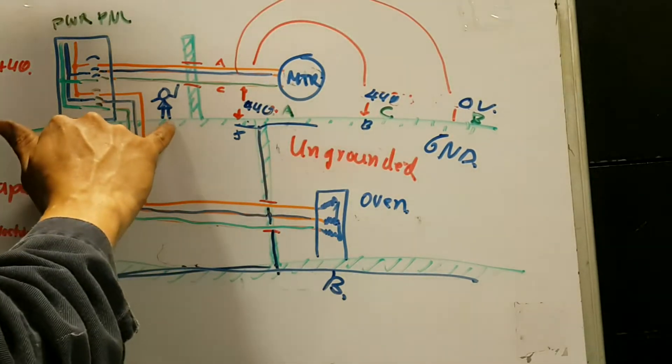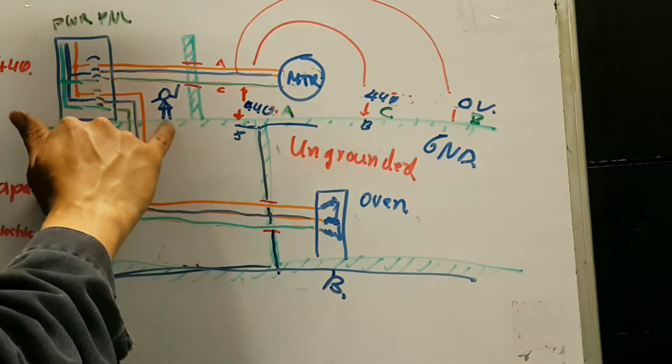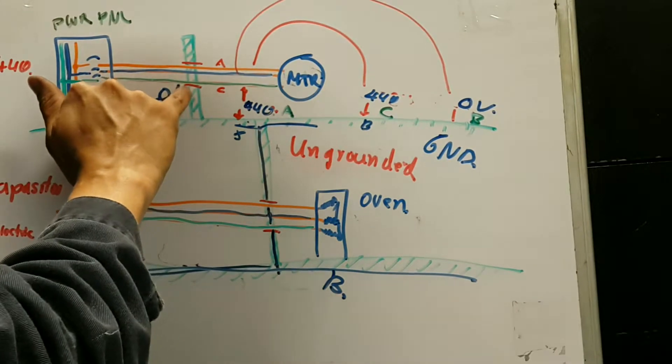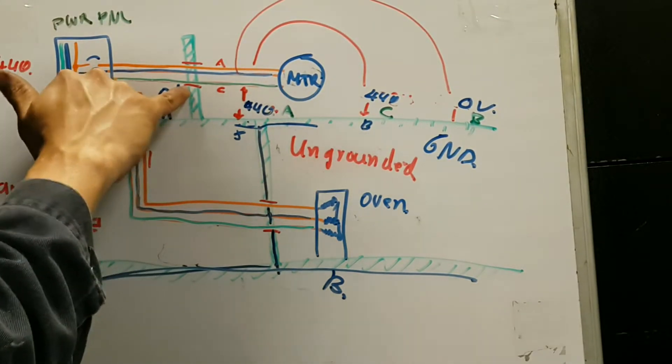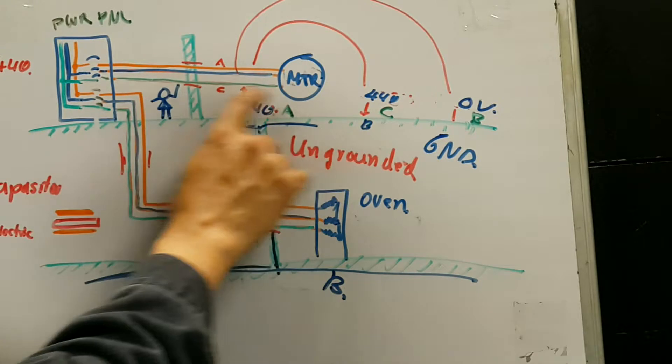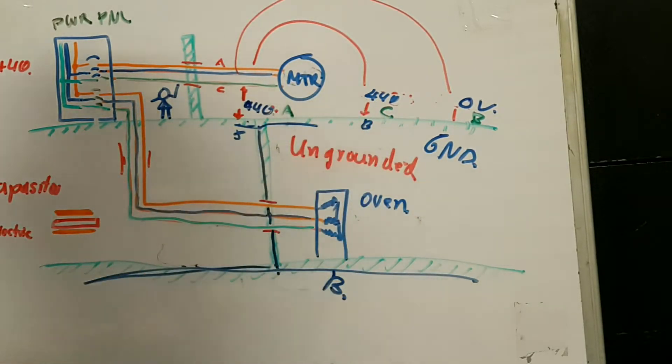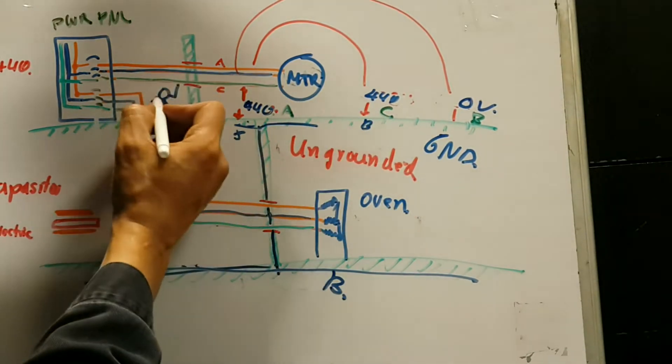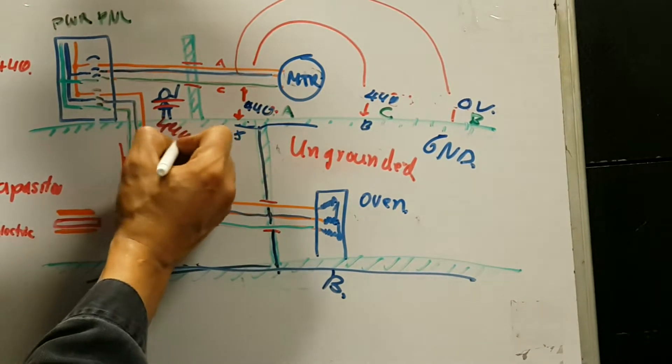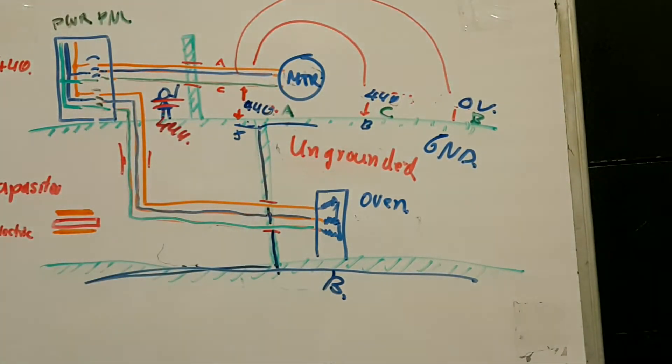Now, what happens if you are standing on the ship barefooted and you touch the Charlie conductor, the C phase? Well, we just learned that now you're not getting shocked by 220, but you're getting shocked by 440 volts. That definitely makes it dangerous in that situation.